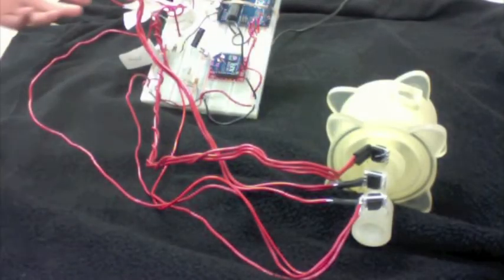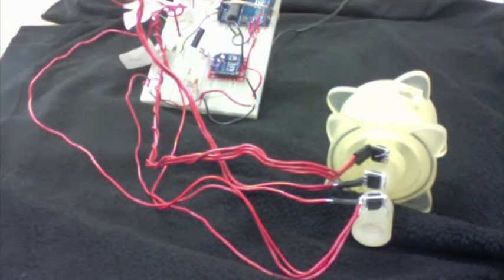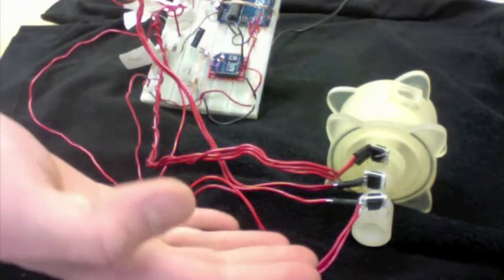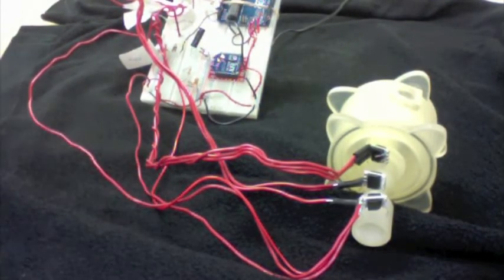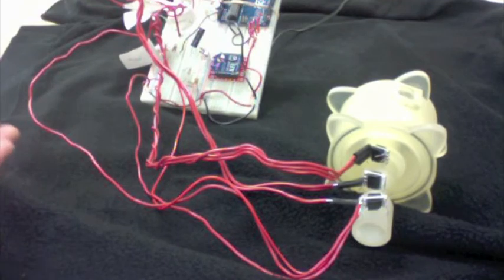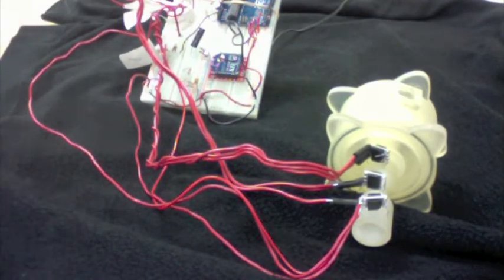What we have here is our data acquisition hardware. Our story begins with 3 Honeywell pressure transducers. They are silicon standard ceramic series gauge pressure transducers, and they are designed to measure from 0 to 250 millibars of pressure. Each pressure transducer will output a signal from 0 to 5 volts depending on the pressure that it reads. Because we are detecting oscillations, these output signals will be AC.